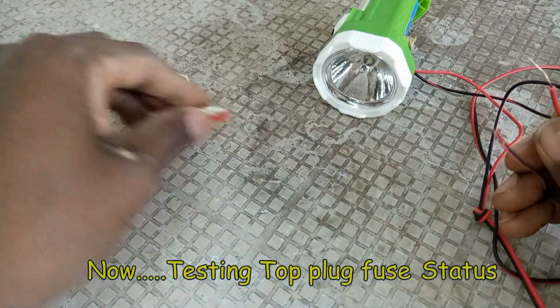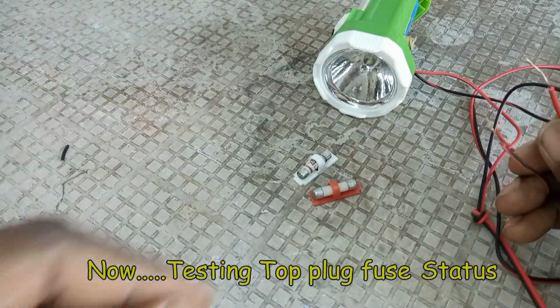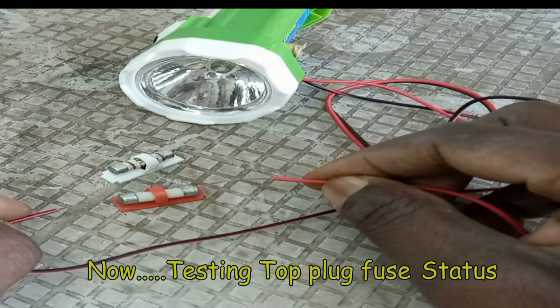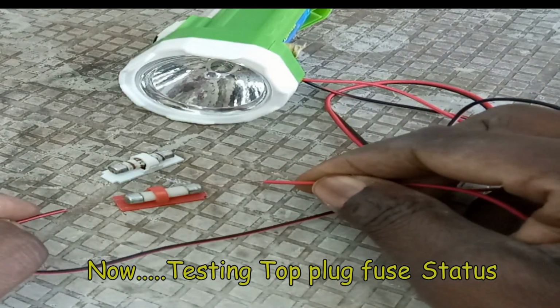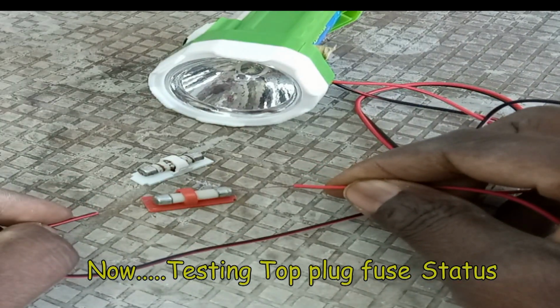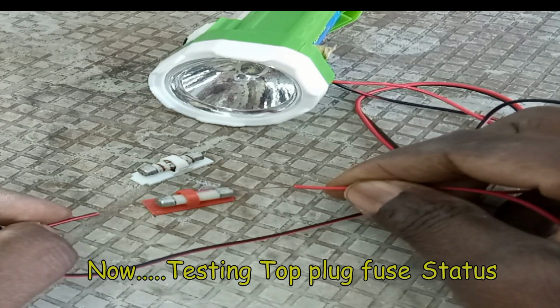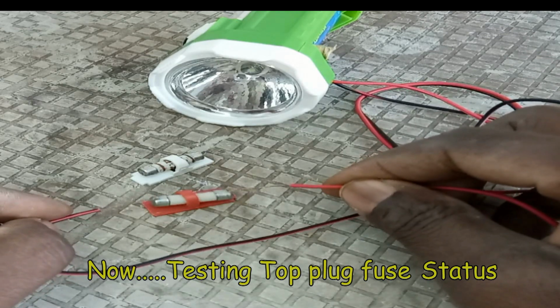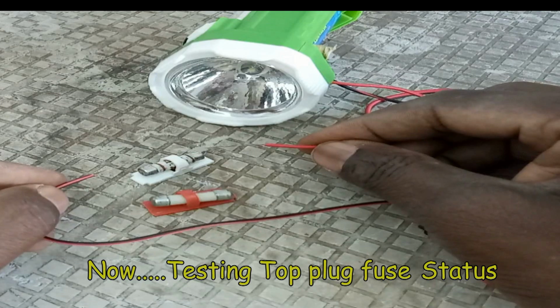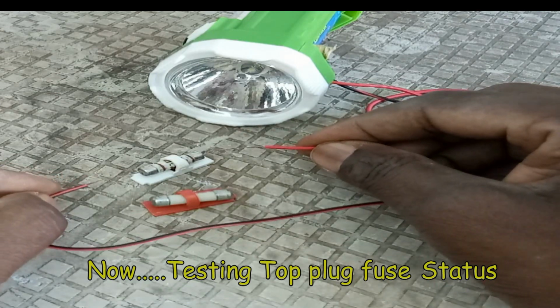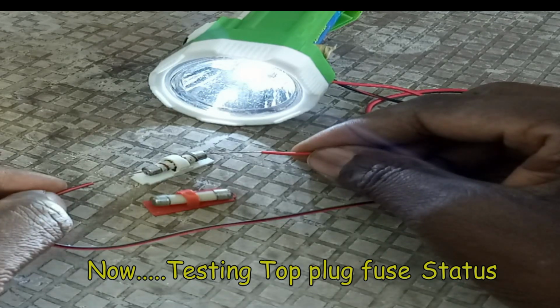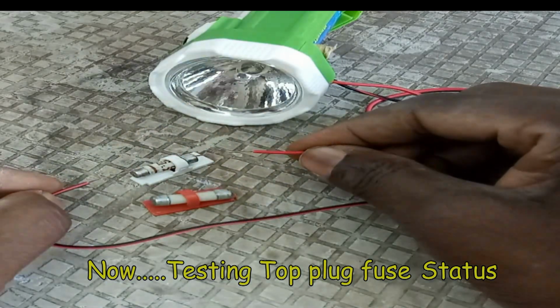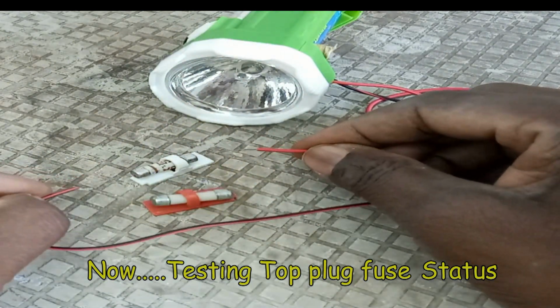You can now use these to test our fuses again. When we touch the two terminals of the first fuse, the torch does not light up because there's no continuity, meaning that fuse is bad. When we touch the two terminals of the second fuse, the bulb lights up, meaning there's flow of current through the fuse—there's continuity, and that fuse is okay.